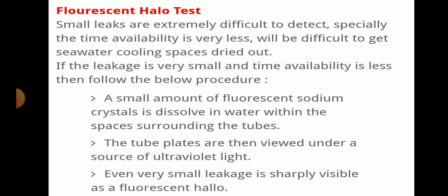With the fluorescent halo test, small leaks are extremely difficult to detect, especially when the time available is very less. So it will be difficult to get the seawater cooling space dried out. So if the leakage is small and time availability is less, we can use the fluorescent halo test.